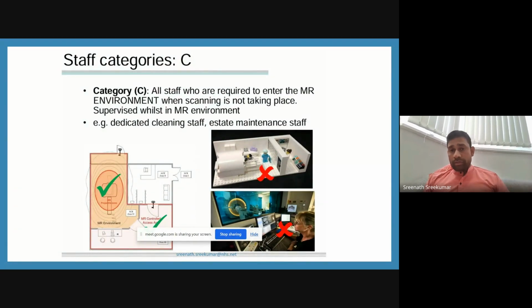Then another staff, which is called category C, who are required to enter the MRI environment when the scanning is not taking place. We can see why the arrow is there. They are not allowed to operate the machine also. They are not allowed to enter while scanning is in progress. Like when the scanning is there, they are not allowed. While we are scanning a patient inside, if somebody comes from maintenance staff, they have to wait to finish the scan, or cleaning staff will wait outside. They are only allowed to go in whilst not scanning. That's why they are called category C.